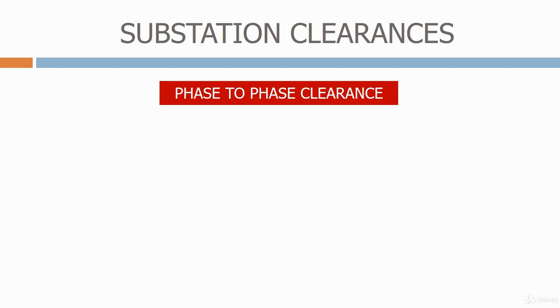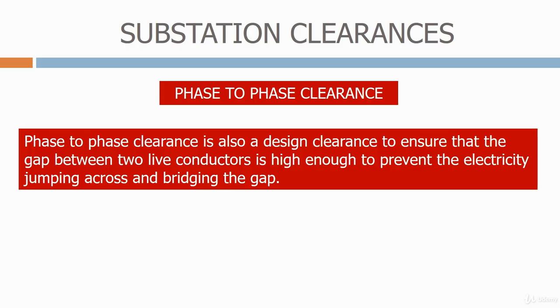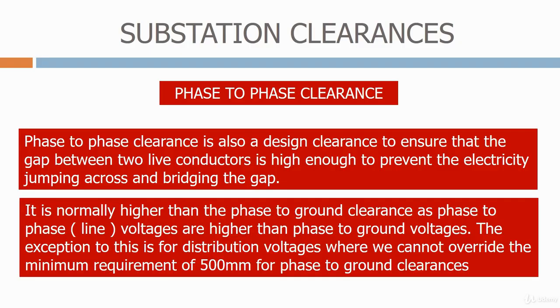Next we have the phase-to-phase clearance. Face-to-phase clearance is also a design clearance to ensure that the gap between two live conductors is high enough to prevent the electricity jumping across and bridging the gap. It is normally higher than the phase-to-ground clearance, as phase-to-phase, i.e. line voltages, are higher than phase-to-ground voltages. The exception to this is for distribution voltages, where we cannot override the minimum requirement of 500 mm for phase-to-ground clearances.